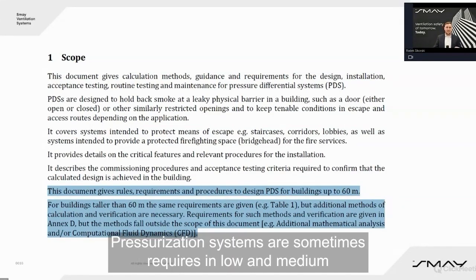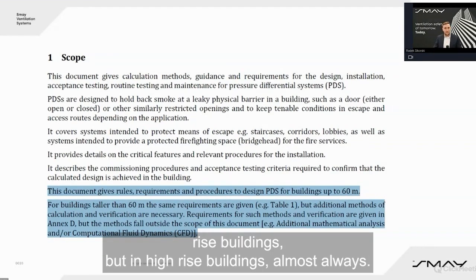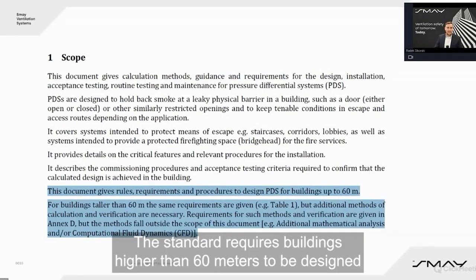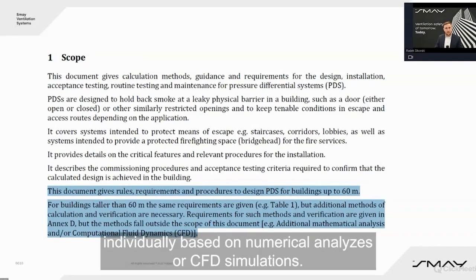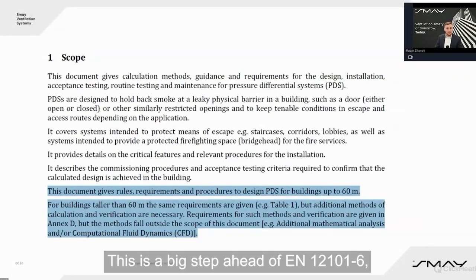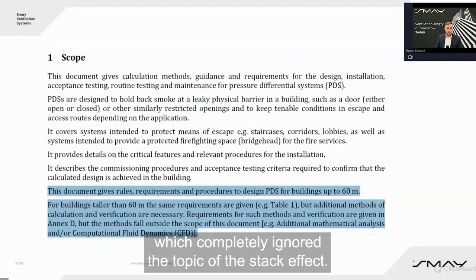Pressurization systems are sometimes required in low- and medium-rise buildings, but in high-rise buildings, almost always. The standard requires buildings higher than 60 meters to be designed individually, based on numerical analysis or CFD simulations. This is a big step ahead of EN 12101-6, which completely ignored the topic of the stack effect.